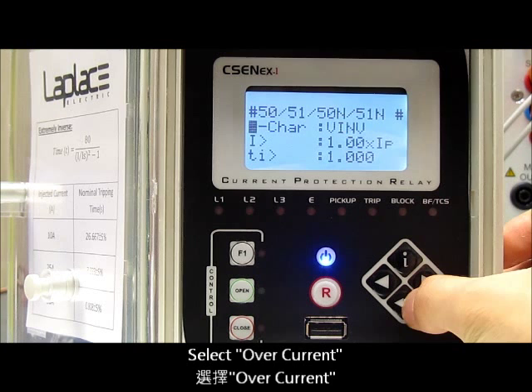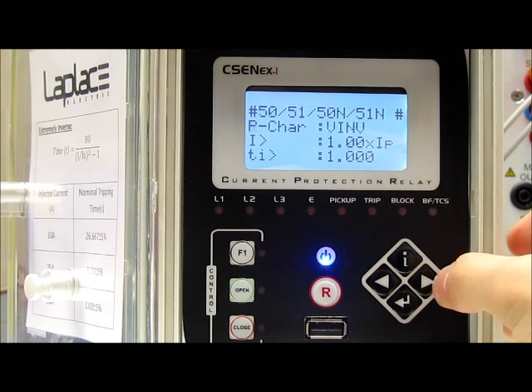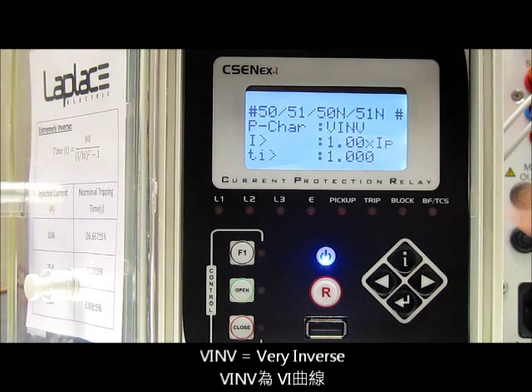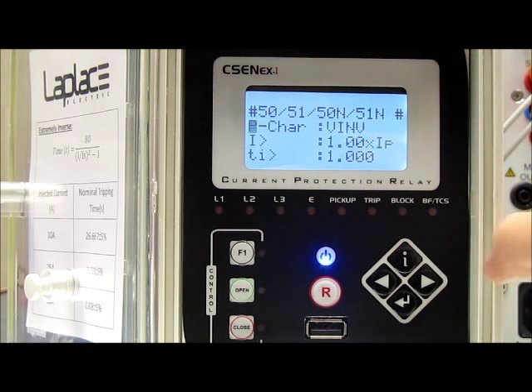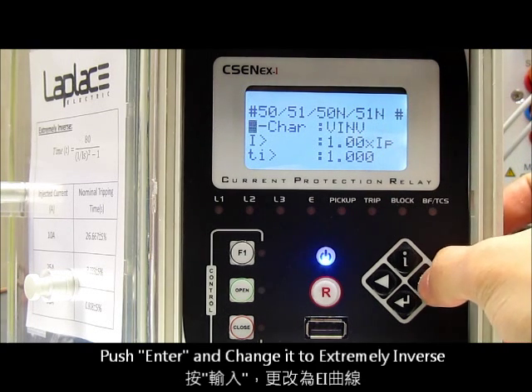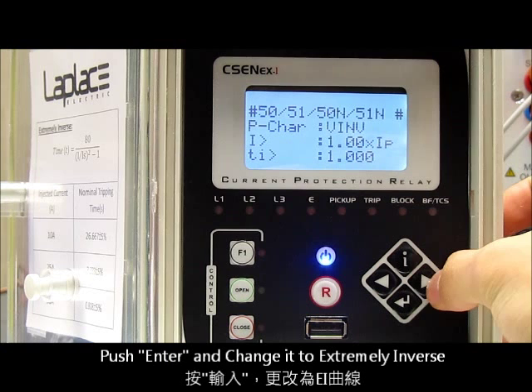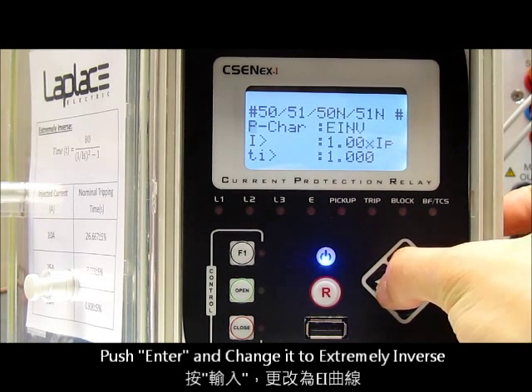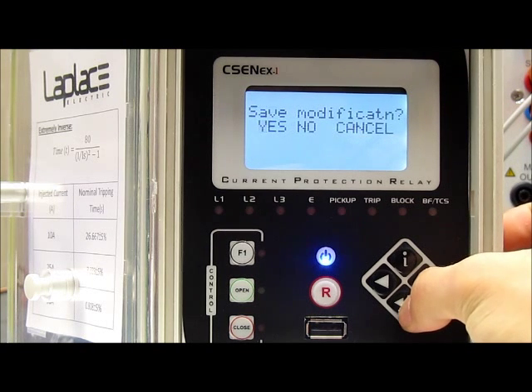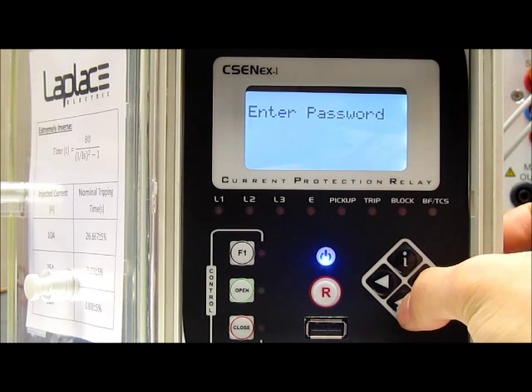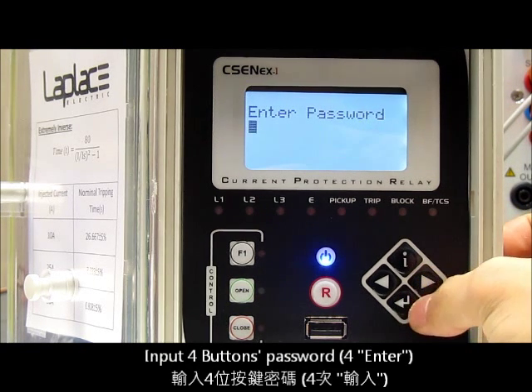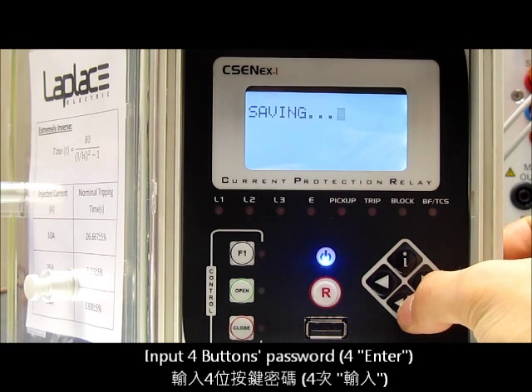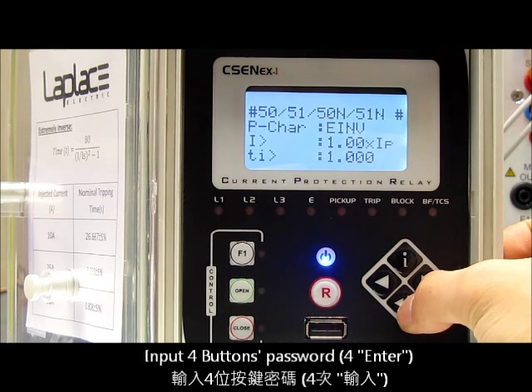Then we go back to the previous page and go to the overcurrent setting. Firstly, we can see the P characteristics — it is set to very inverse. We push the enter button, change it to extremely inverse, and push enter four times. Okay, finish.